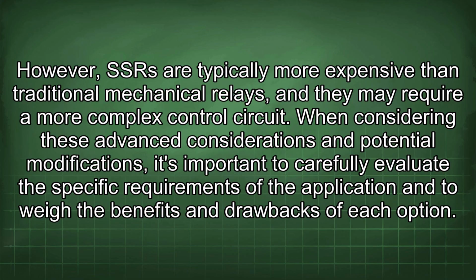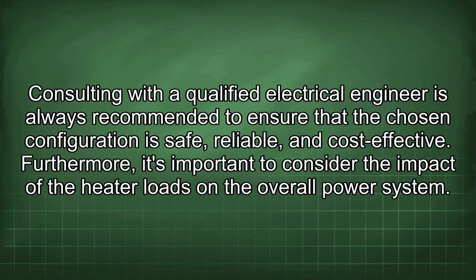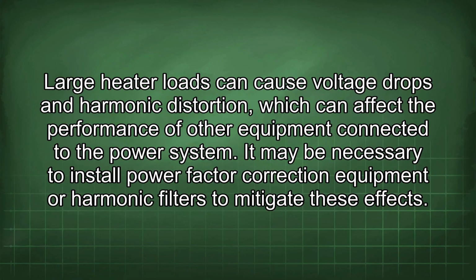When considering these advanced considerations and potential modifications, it's important to carefully evaluate the specific requirements of the application and to weigh the benefits and drawbacks of each option. Consulting with a qualified electrical engineer is always recommended to ensure that the chosen configuration is safe, reliable, and cost-effective. Furthermore, it's important to consider the impact of the heater loads on the overall power system. Large heater loads can cause voltage drops and harmonic distortion, which can affect the performance of other equipment connected to the power system. It may be necessary to install power factor correction equipment or harmonic filters to mitigate these effects.